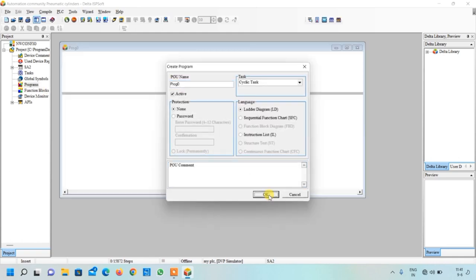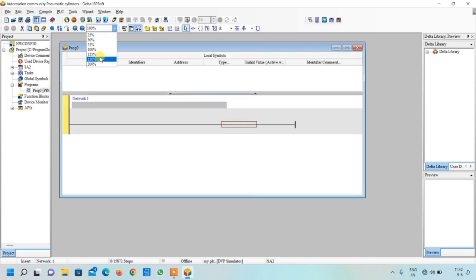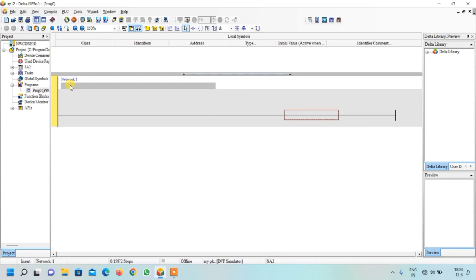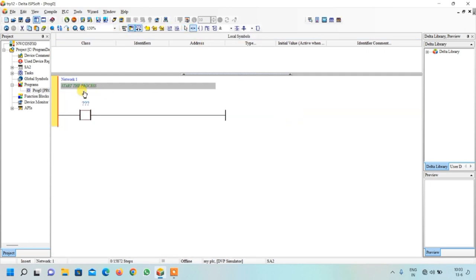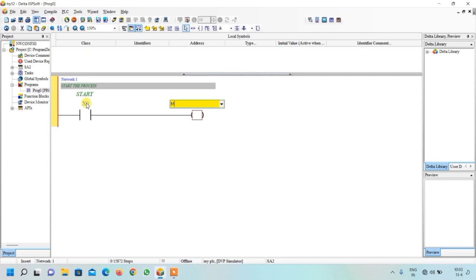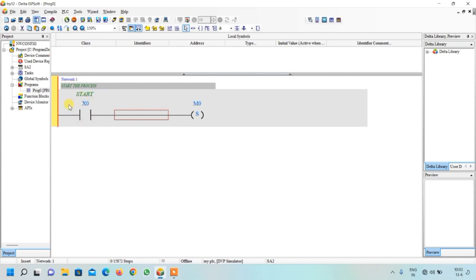Close the device comment box, right-click on programs file, click on new file, and click OK. Maximize the window and write a network comment. Here we are going to use the start button and one internal relay M0 to start the process. Select contact from here, select output coil, give address X0, press Enter, and write M0. Double-click to select Set — when the user presses and releases the start button, M0 will be set to keep our process on.